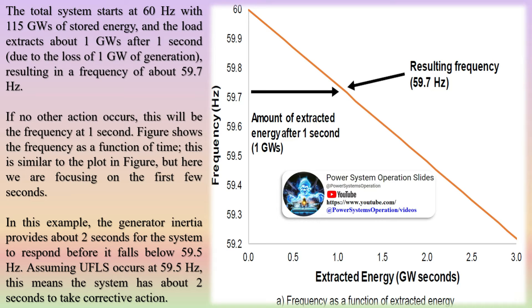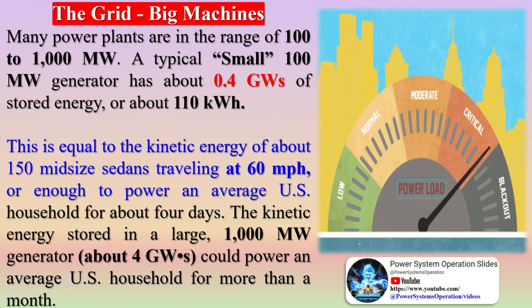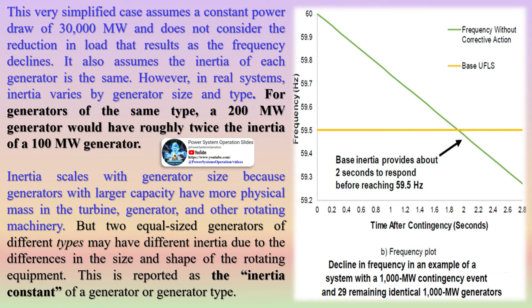Two equal-size generators of different types may have different inertia due to differences in the size and shape of the rotating equipment. This is reported as the inertia constant of a generator or generator type. Inertia scales with generator size because generators with larger capacity have more physical mass in the turbine, generator, and other rotating machinery. The combination of inertia constant and total capacity of online generators determines the total inertia provided by the generators.